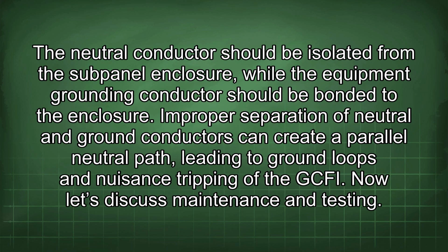The neutral conductor should be isolated from the sub-panel enclosure, while the equipment grounding conductor should be bonded to the enclosure. Improper separation of neutral and ground conductors can create a parallel neutral path, leading to ground loops and nuisance tripping of the GFCI. Now let's discuss maintenance and testing.